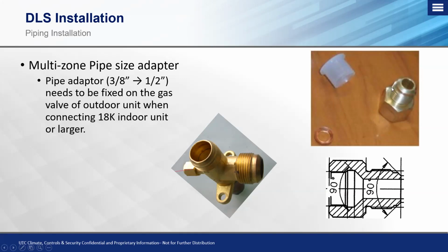And then from there, on this side is where we take our pipe that comes from the indoor unit that's flared and has a nut, and this is where we're hooking up that connection. Okay, if you don't have one of these copper fittings that came with your adapter, please give me a call. I carry a bunch of them as backup, and I can always send you out one, depending on if you need one or if you need 5 or 6. Just please make sure that that's inserted in there. Otherwise, you're going to have a very large leak.